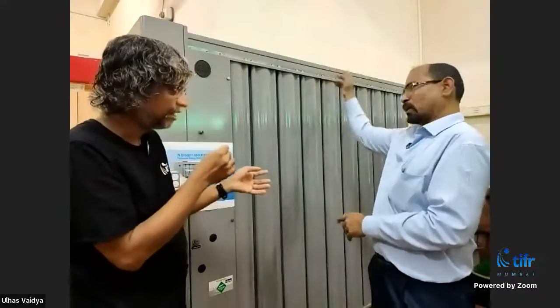In 4 minutes, this is full of oxygen and can't absorb anymore, so you switch to the other set which absorbs the oxygen, while this one is flushed out with some of the nitrogen pushing the absorbed oxygen out, and we just release it.